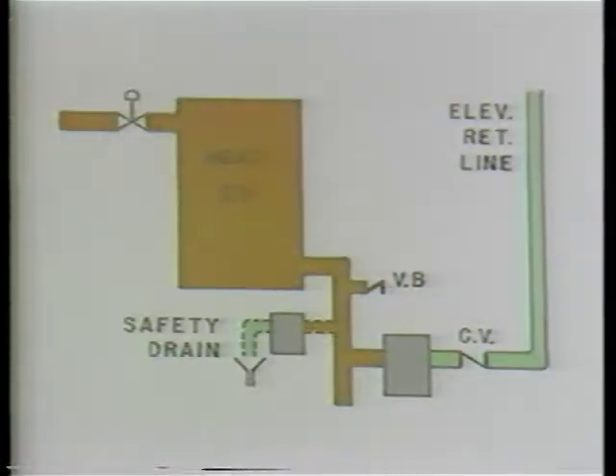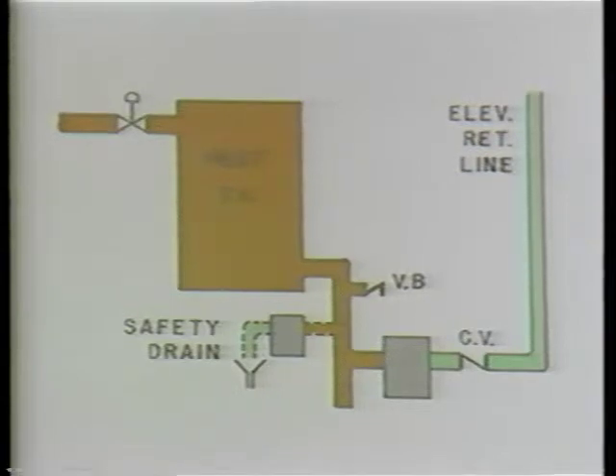Elevating condensate should always be avoided. However, if it is absolutely necessary, a safety drain and a check valve should be provided. The safety drain will discharge the condensate load only when the pressure is insufficient to lift the condensate to the return line, while the check valve will prevent the backflow of condensate into the coils.